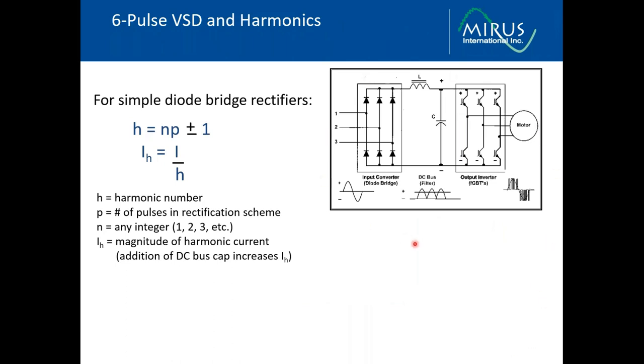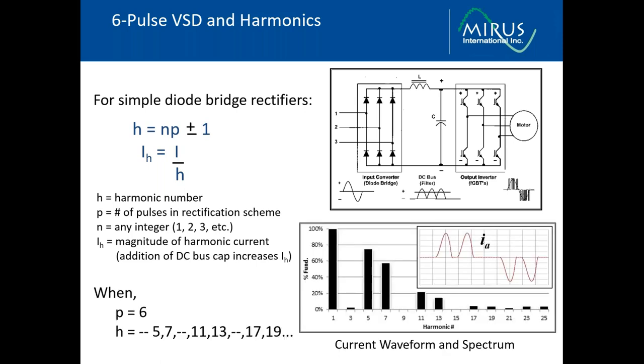Here we show the schematic for a typical six pulse variable speed drive. We've got the input rectifier, three phase six pulse rectifier. There's often DC line chokes. We've got our smoothing capacitors on the DC bus. And then that supplies an inverter section, which takes the DC and inverts it back to a simulated AC waveform for the motor. In this operation, the rectifiers will draw harmonic currents in this relationship, where the harmonic numbers present will be equal to any integer times a pulse number plus or minus one. And typically the magnitude of each harmonic current is inversely proportional to the harmonic number.